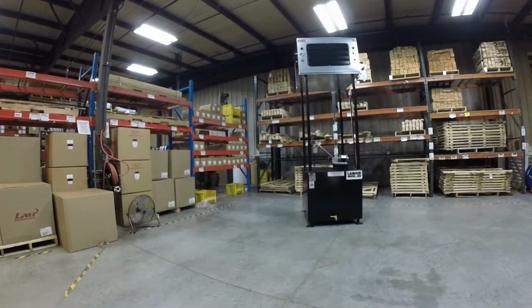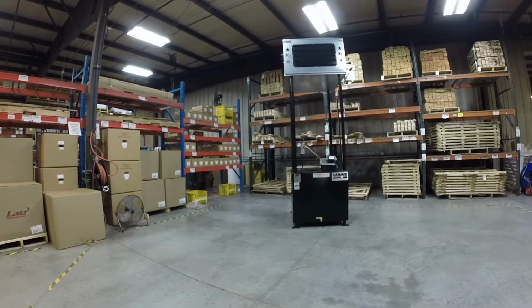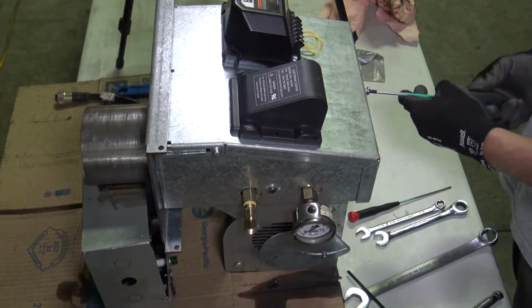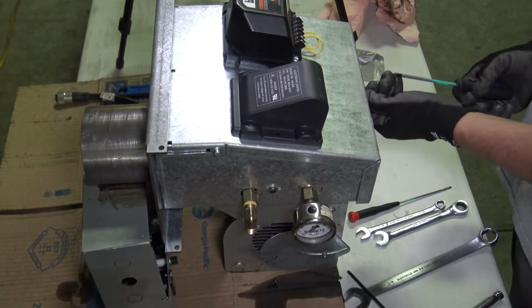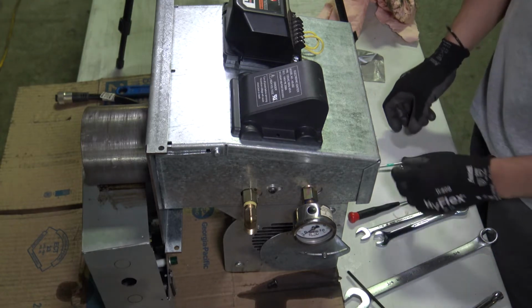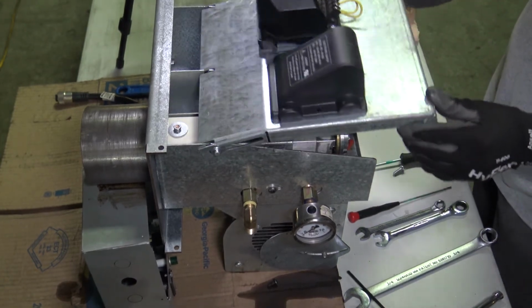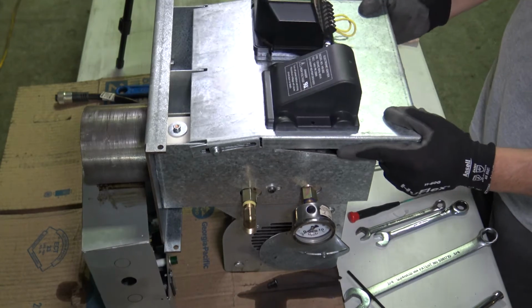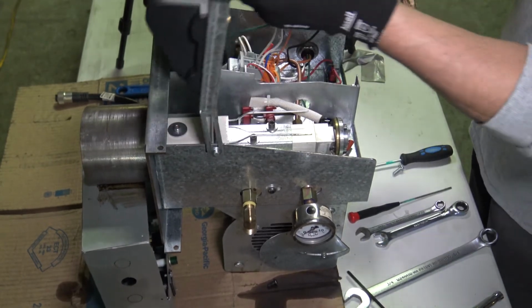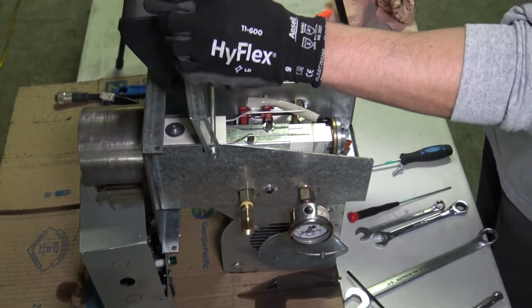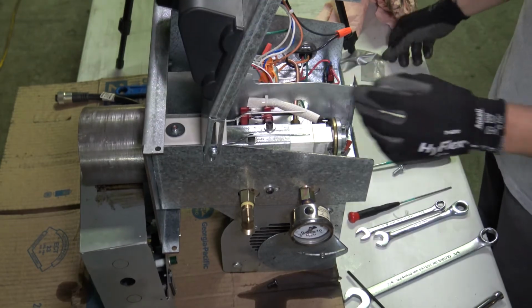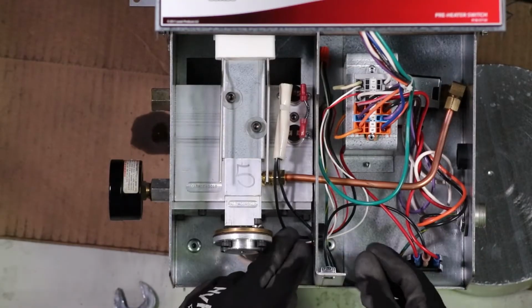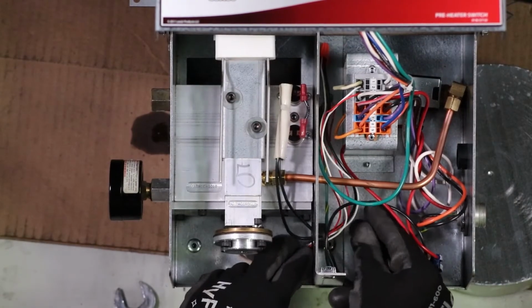Depending on the system's configuration, it may be easier to work with the burner still mounted to the heater cabinet or removed and brought to a workbench. Either way, you will need to be positioned to open the burner and look down into it while working, and remain safe and stable even with shifting weight distribution. With the power off and the burner cord, air line, and fuel supply all disconnected from the burner, open the burner and locate the preheater assembly within.